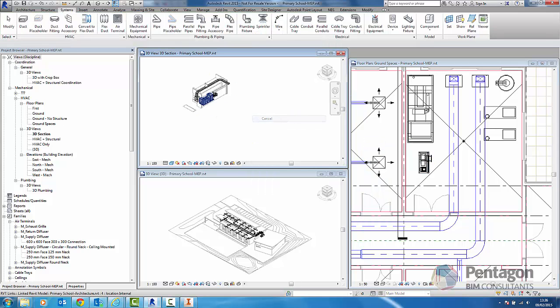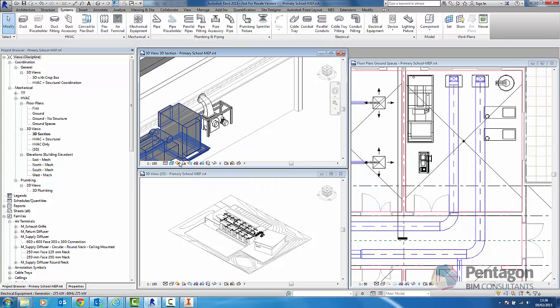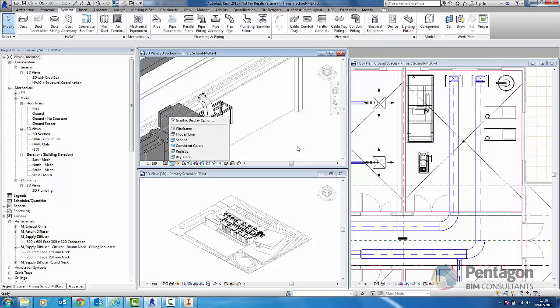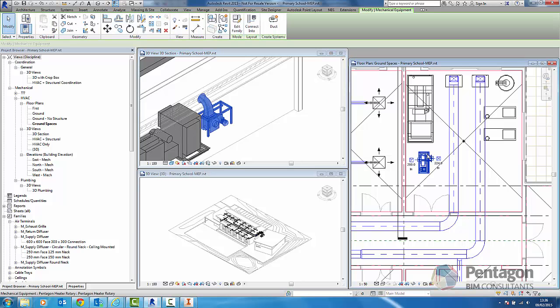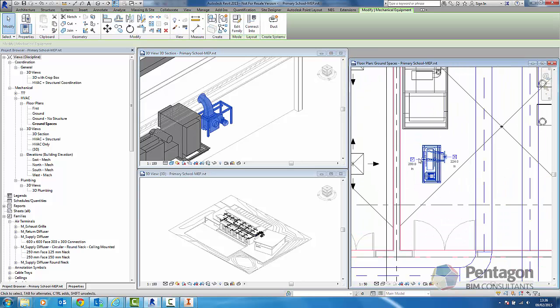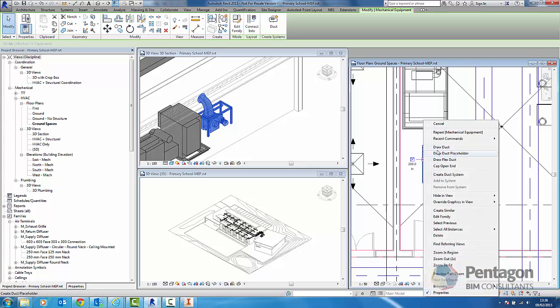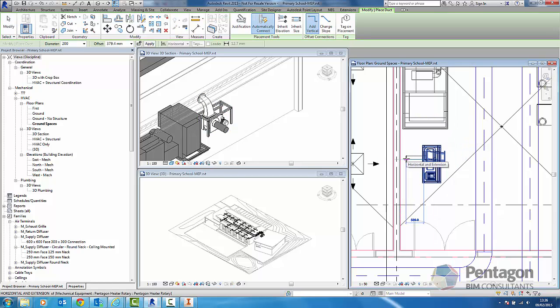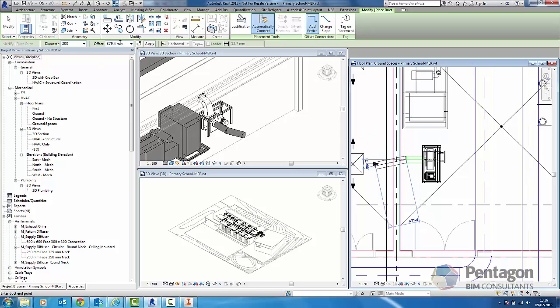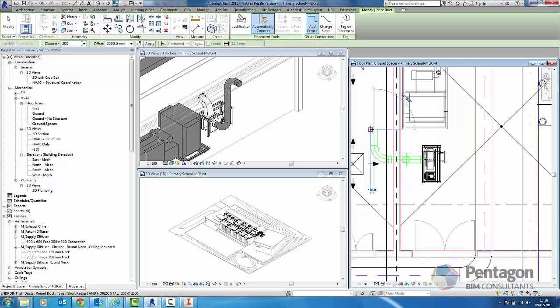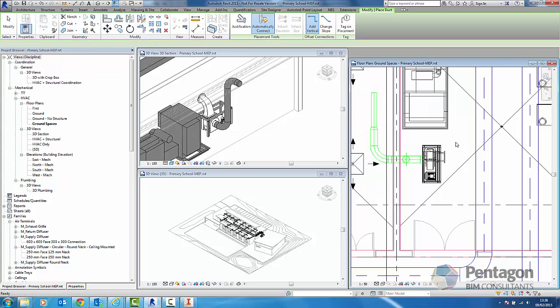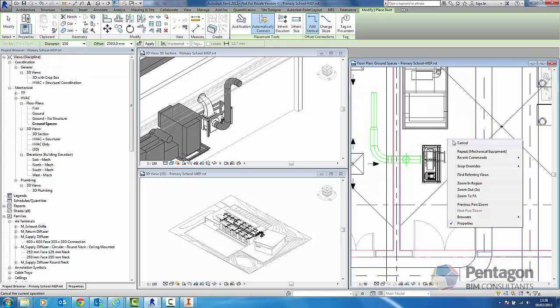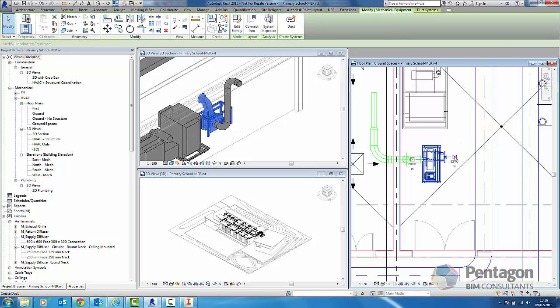We can see that in our 3D view and we can actually start connecting and working with the object. You can see the connections in here. If I simply right click it'll allow me to draw a duct and I can start to add this information in. It's working within the Revit parameters so I can add in a transition or a T etc. I can reduce the size of it as well so it's going down to 150 and allowed the appropriate transition in there. Same goes for supply and exhaust as well.